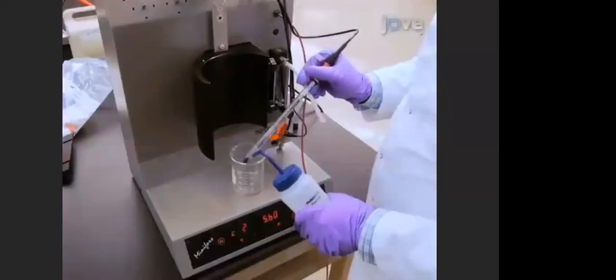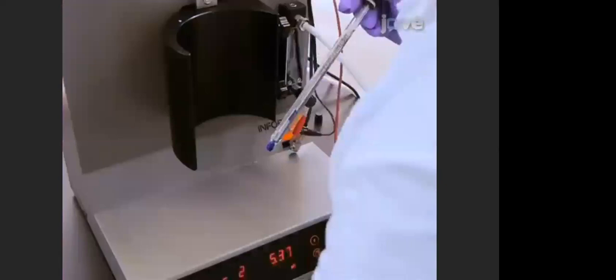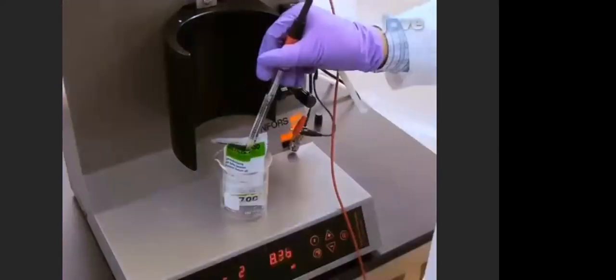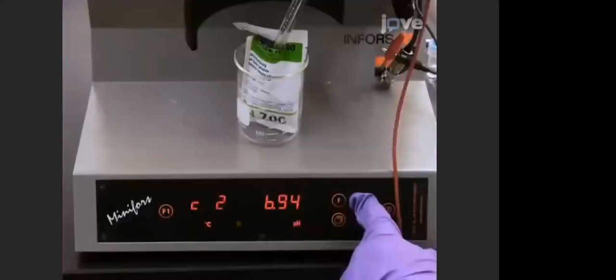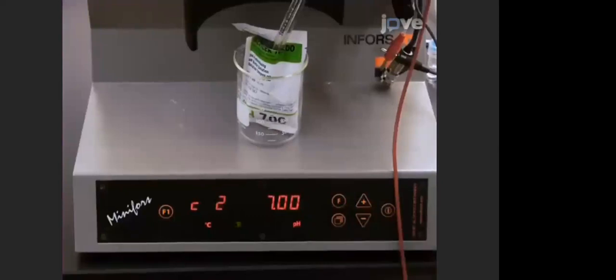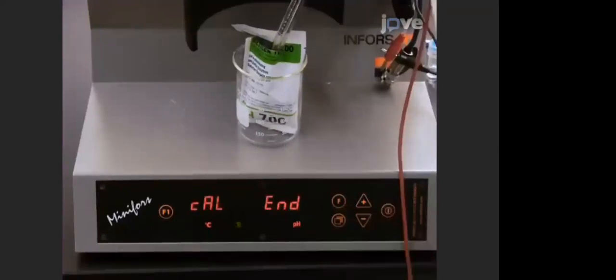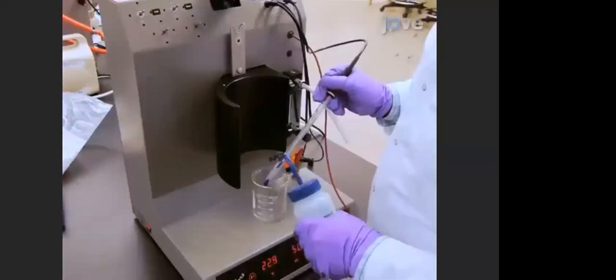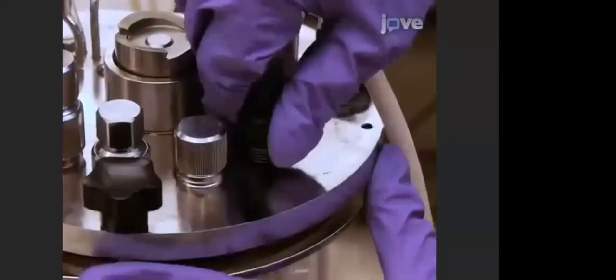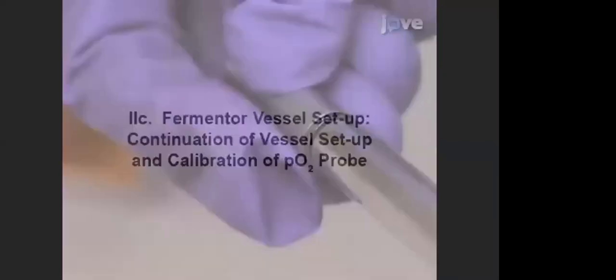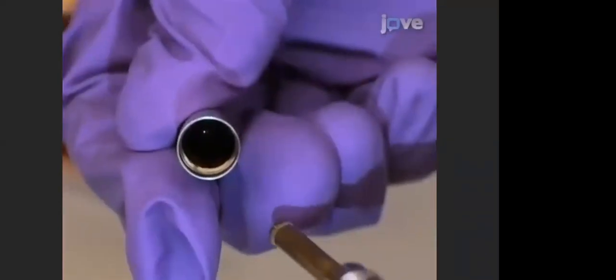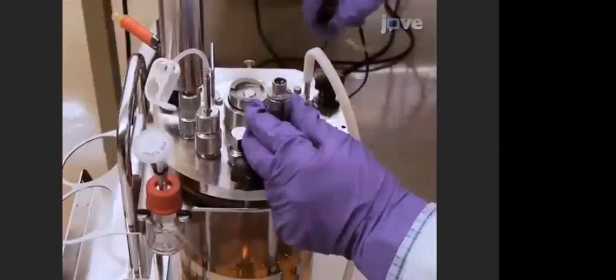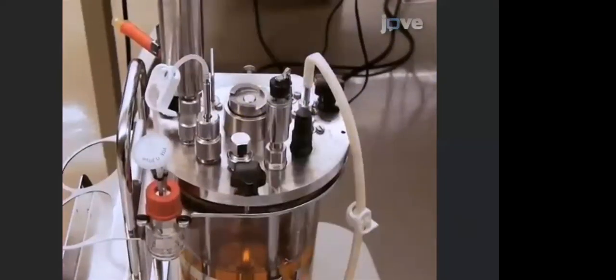Next, wash the low reference buffer off the probe and insert the probe into the second reference buffer. Allow the value to stabilize, and then use the keypad to make the displayed value match the high reference buffer value. Press Enter to confirm. Wash the probe tip and disconnect it from the fermenter. Put the protective cap on the connection and install it in the head plate. Open the oxygen probe tip and check to ensure that there is enough electrolyte to cover the tip. Install the oxygen probe in the head plate. Make sure the autoclave cap is put on to protect its electrical connections, as it will be sterilized prior to calibration.